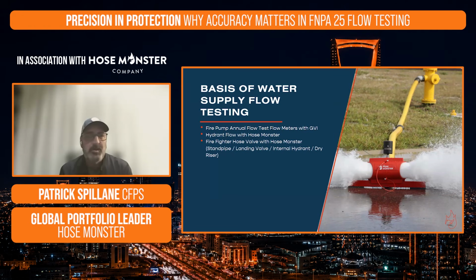So everything that we do here at Hose Monster is all around the basis of water supply. So that's why we test fire pumps with an annual flow test. Whether you're flowing water externally with a Hose Monster device to challenge that fire pump, or using a flow meter like our GVI flow meters to measure the output of that fire pump. Performance hydrant testing, making sure that the fire hydrants are adequate and up to the task for the fire department to hook up to in the event of a fire. As well as the hose valves inside the building, the firefighter hose valves.